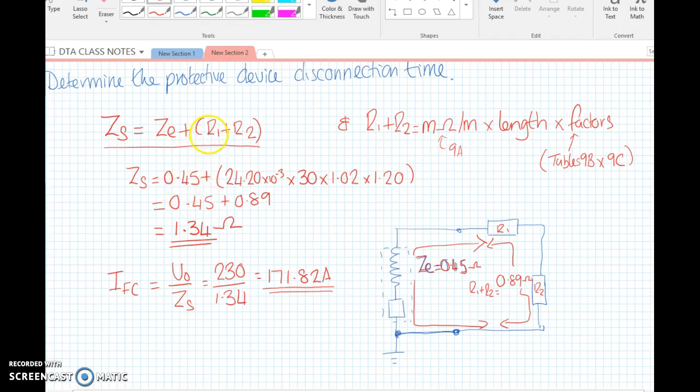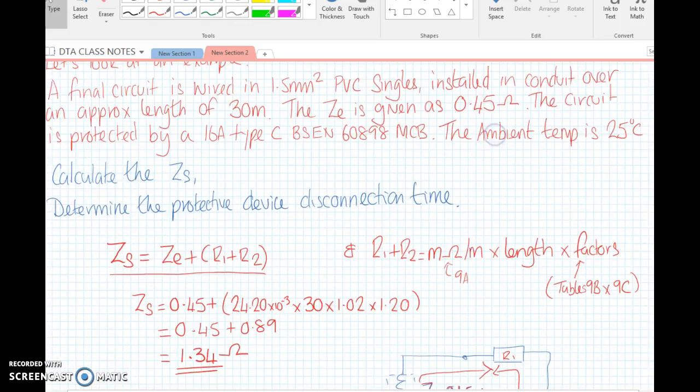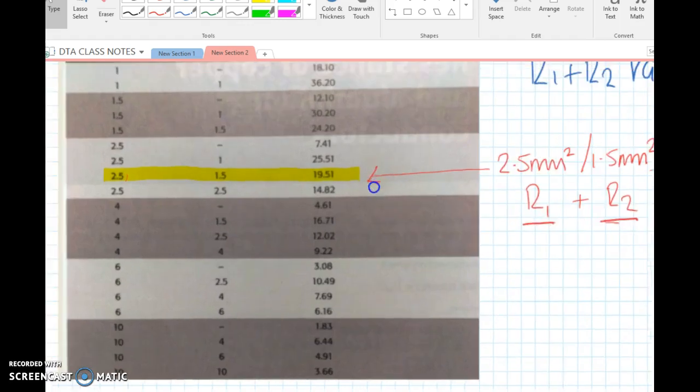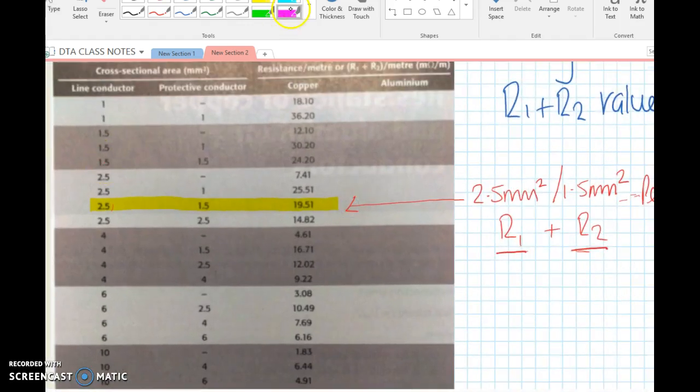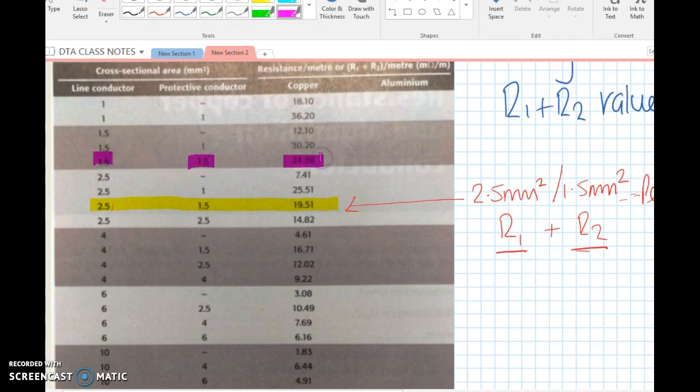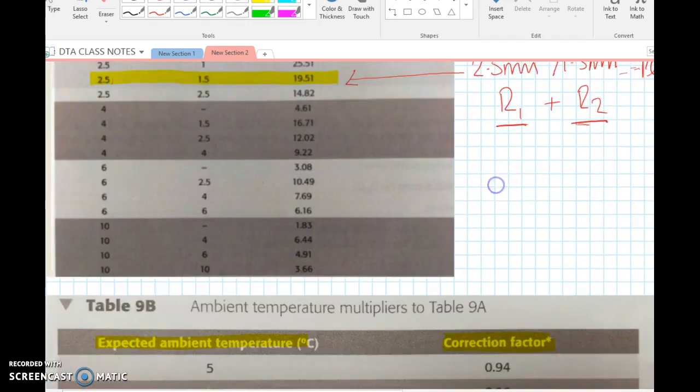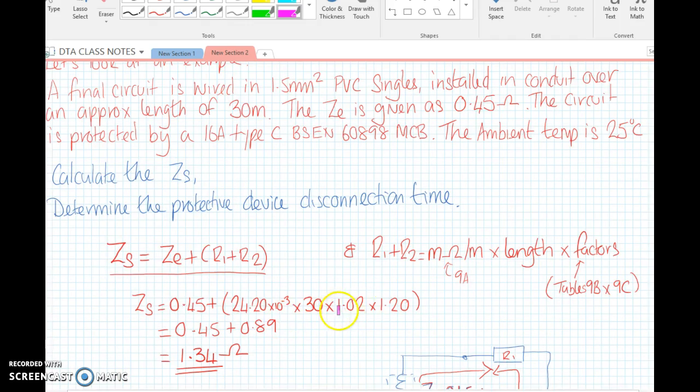Our external impedance is 0.45 ohms, and our R1 R2, well it's a 1.5 cable. A 1.5, 1.5 has a resistance of 24.2 milliohms per meter, so we'll drop that in there: 24.2 times 10 to the minus 3 ohms. Now let's look at the other factors. The ambient temperature of the brief gave it at 25 degrees, so we're going to multiply it by 1.02, that increases the resistance ever so slightly.